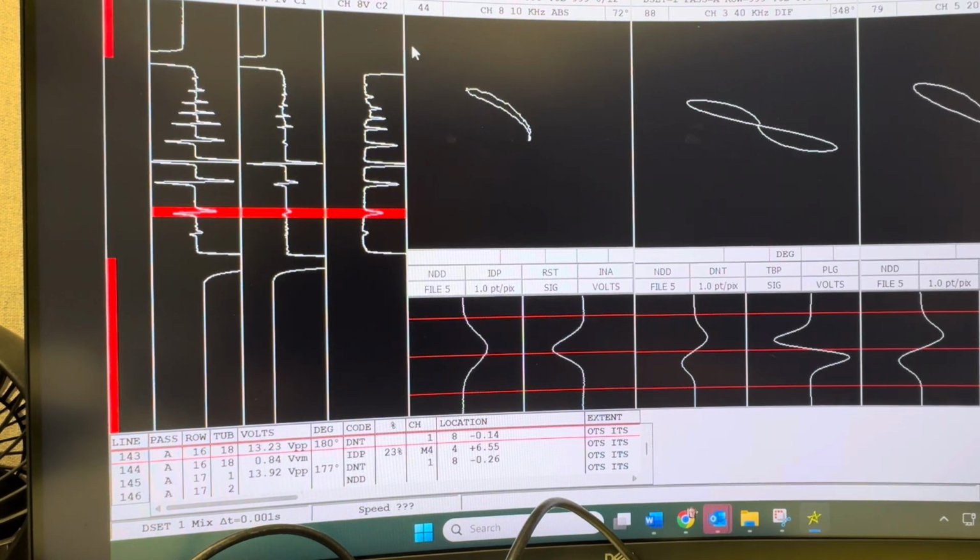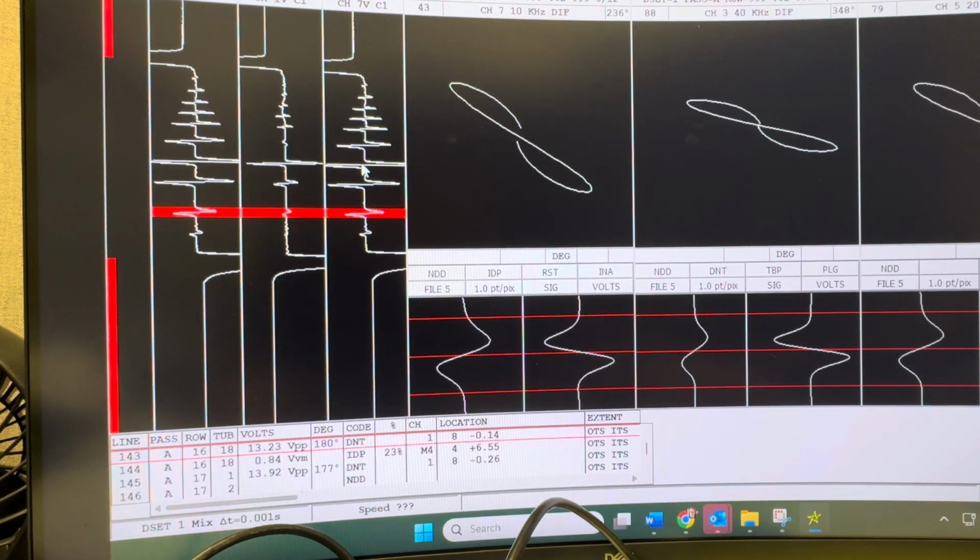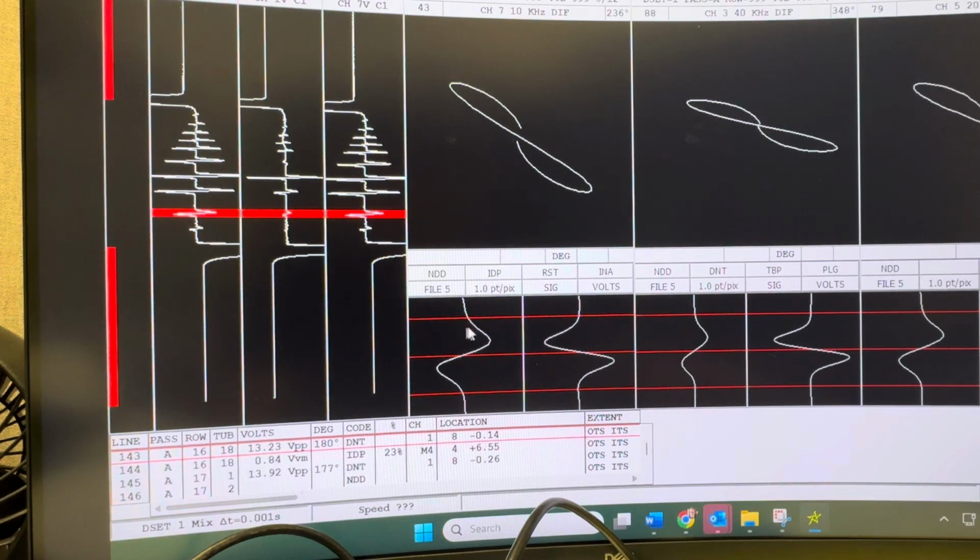And then for your 3rd coil, which is 240 degrees away from your 1st coil, whatever channel that is, you'd put that here. Let's just say it was 7, for example. And then you would take the data from the 3rd coil, and you would do the shift, drag. Oh, you got to be down here. Remember, you got to be in the expanded strip chart window.